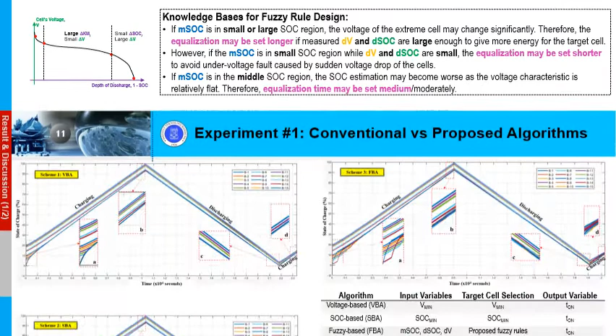For the first experiment, we compare the proposed algorithm with the conventional voltage-based algorithm and the state of charge-based conventional algorithm. The conventional algorithms seem to have no difference in the results, while the fuzzy algorithm has been proved to have a larger equalization step when the state of charge distribution mean is at the extreme values, as near the empty value and near the full value.